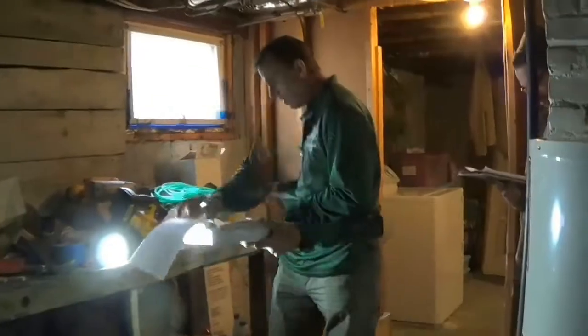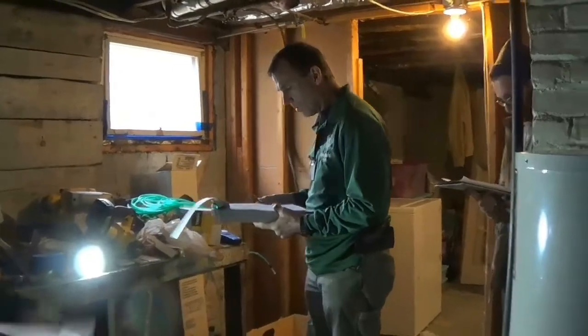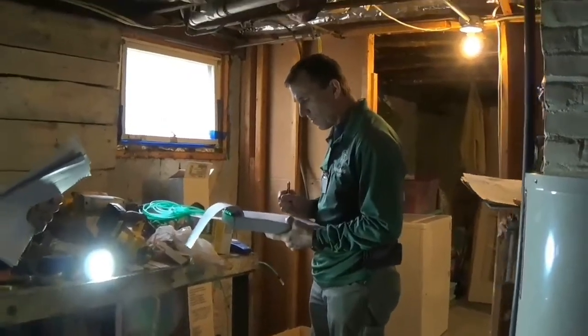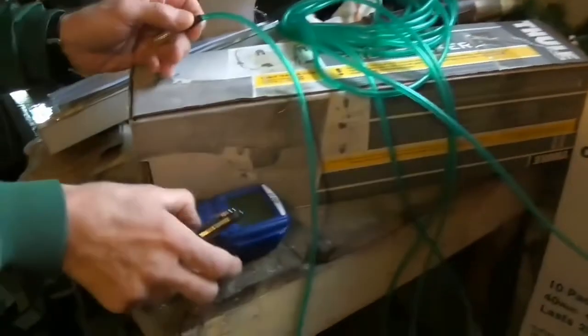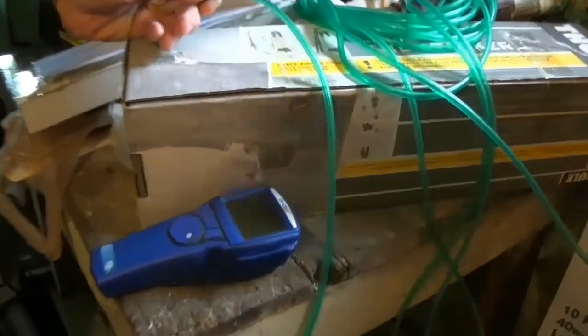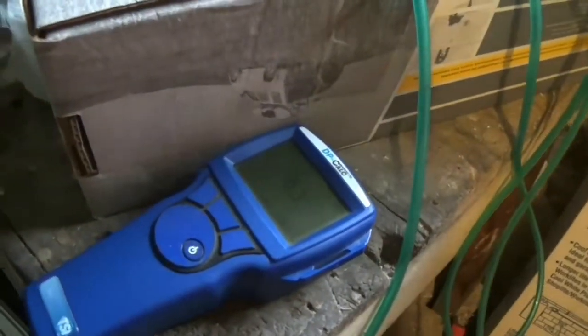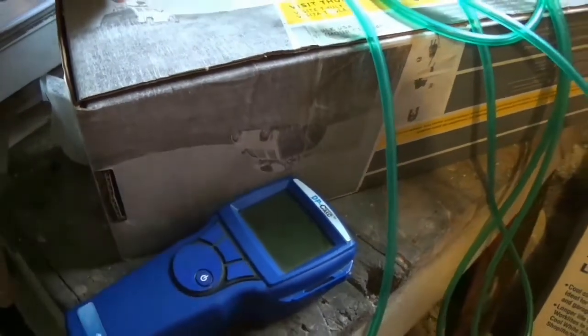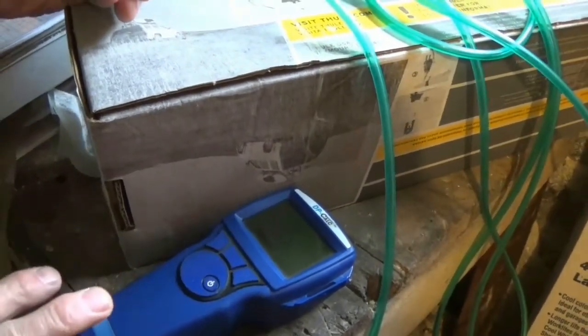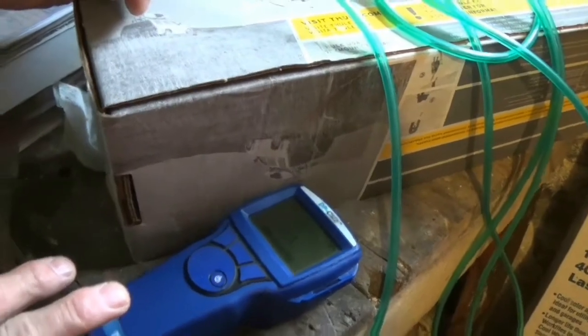Very important. We are getting ready to measure baseline pressure. So I've got a hose already taped up in this window. It's out to the outside world. I have my manometer here, and I'm going to turn the manometer on first. Sometimes what you want to do is zero this thing out before you hook the hose up. So you have a button over here on the right, you can press it. You want to make sure this is sitting still. You don't want to be holding it in your hand and waving it around when you do this.